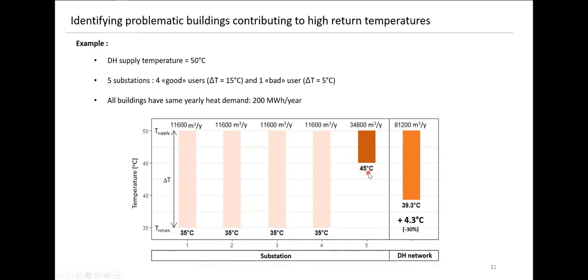In this example, only this one bad substation causes the average mixed return temperature of all five substations to be 39 degrees — more than four degrees higher than it would otherwise be. So one substation can have a substantial effect, as we will also see in the case study.